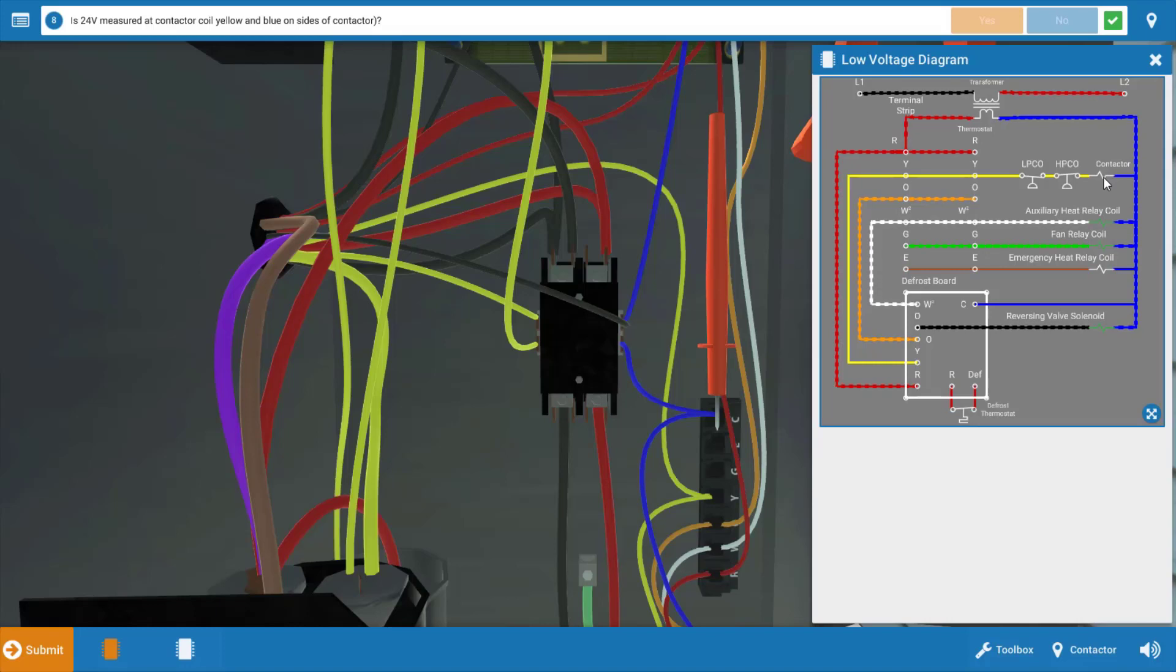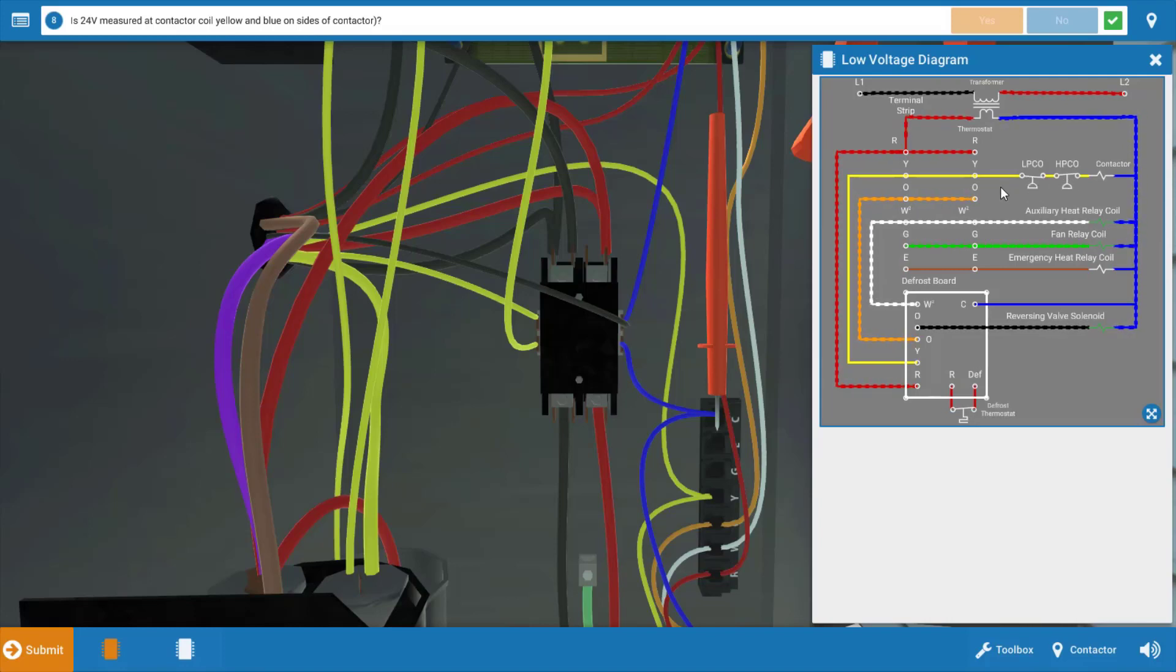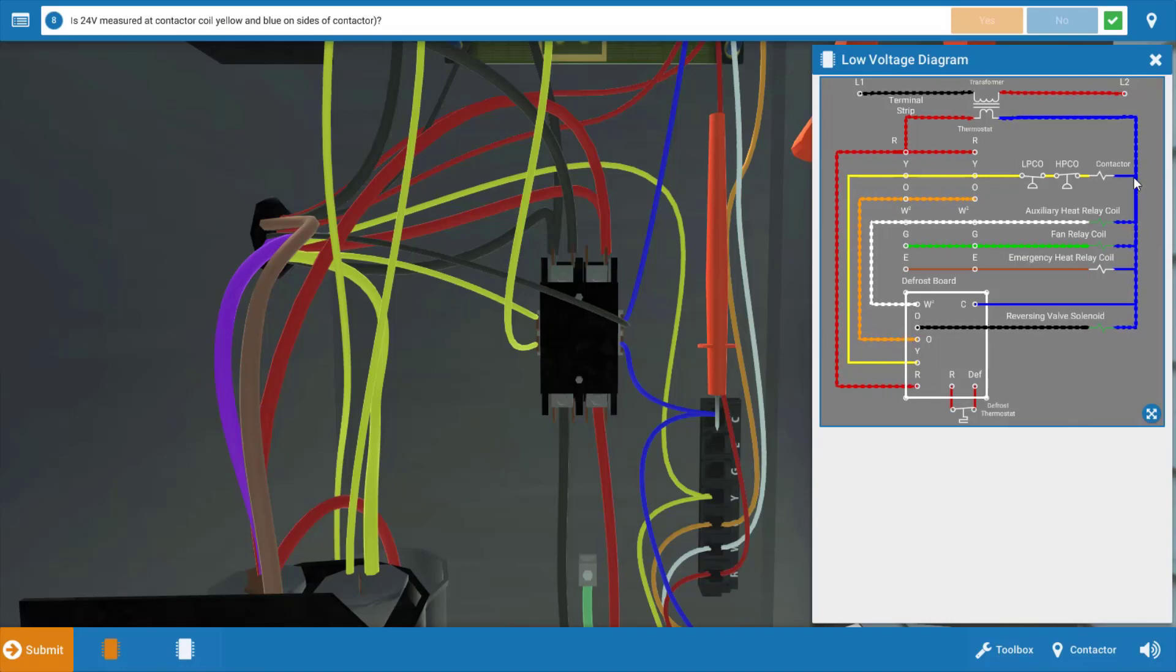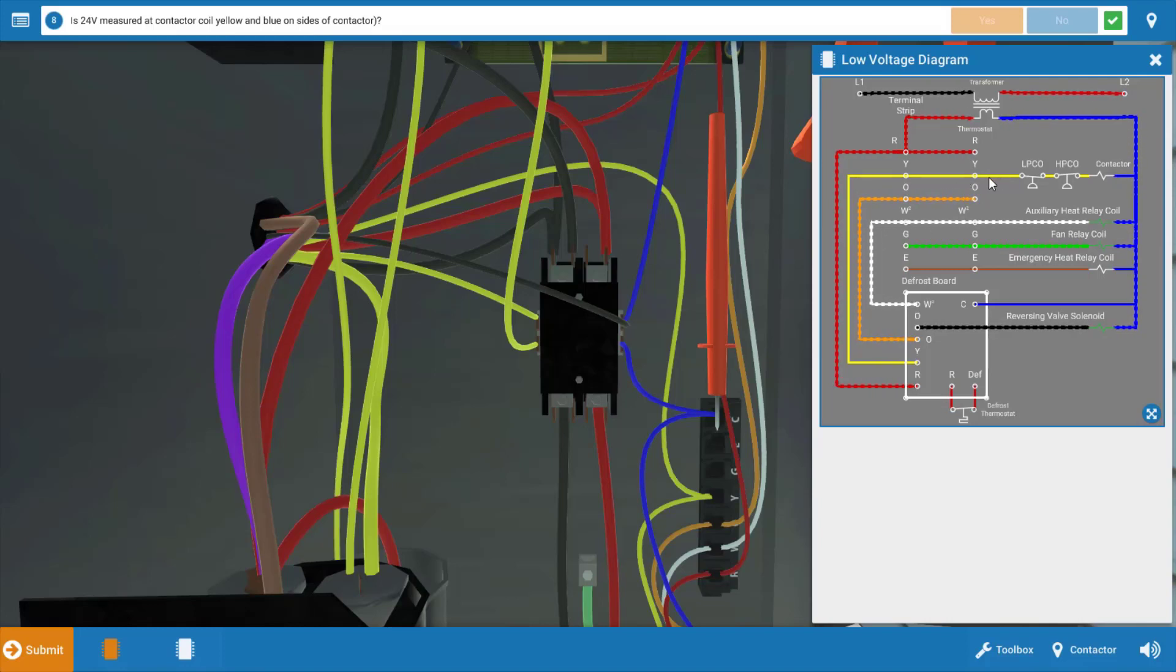It's also possible that we have an open pressure switch in series to the contactor. Now, we could have a faulty switch, but more than likely, if one of these is open, we have a mechanical issue such as a dirty coil or a refrigerant leak or poor airflow inside. In addition to that, the contactor is fed 24 volts through the pressure switches out of the thermostat Y terminal.